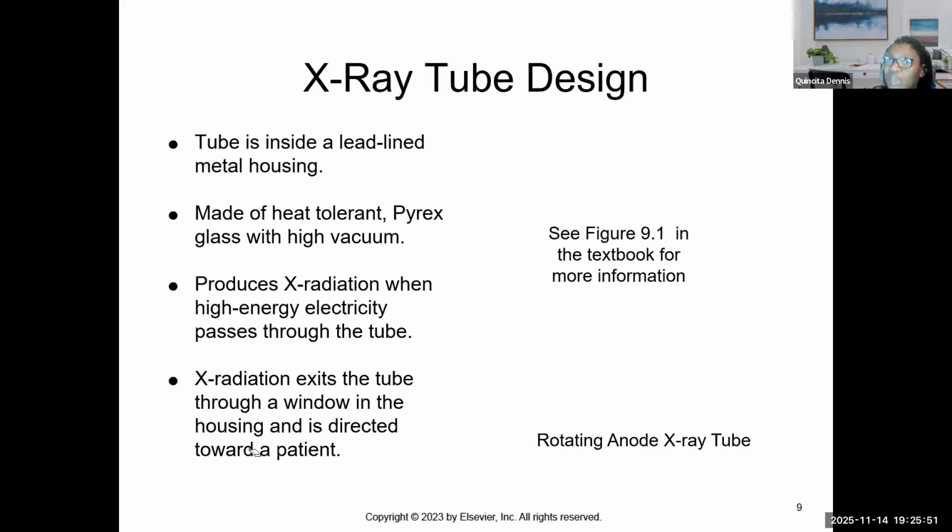So when you go to the actual tube, I don't know if we can see it on the simulator, but if you were to look underneath the tube, you will see it's like a plastic window. And on the plastic window, there's a crosshair that tells you where the center is. You can't see within there, but inside of that is also where the collimator is housed, and the collimator is made up of lead shutters, a light source, and also mirrors to reflect the light to show us exactly where we are.